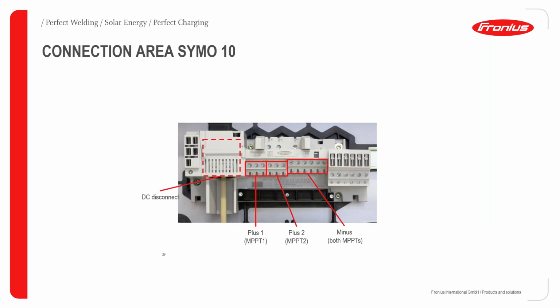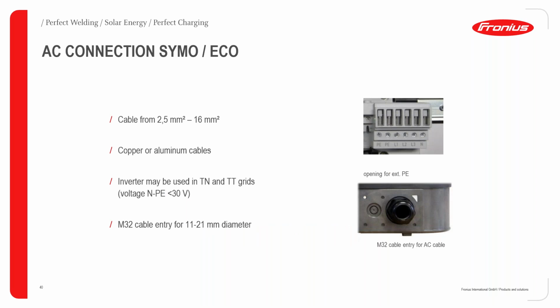So we can now see the different ways that the connection points on the wall mount bracket are situated. So from the DC disconnection point to the strain relief to the MPP plus for MPP1 and MPP2, and then of course the minus or negative terminals, and of course the AC termination screws. So we also have preparations already made in case you're coming in with larger cables or conventional cables for connection, ranging from 2.5 mm to 16 mm. And then, of course, we can go as far as higher cable sizes, which can go up to 21 mm cable diameter.